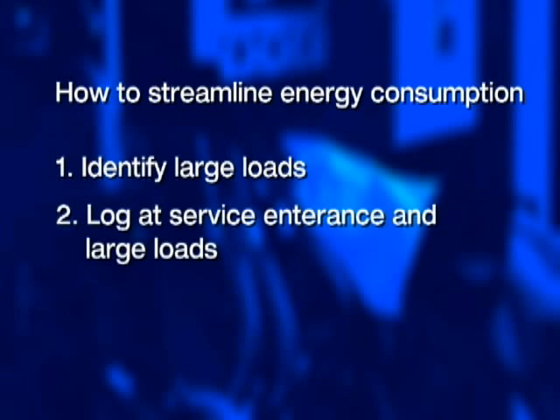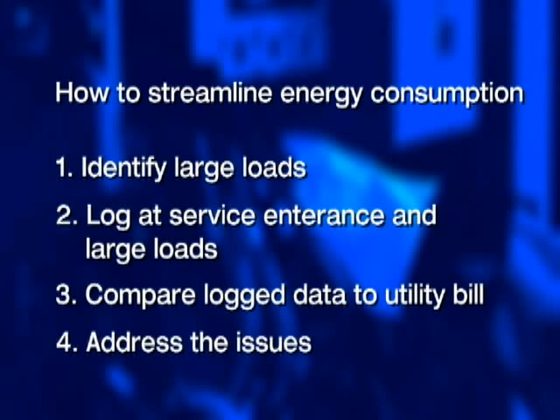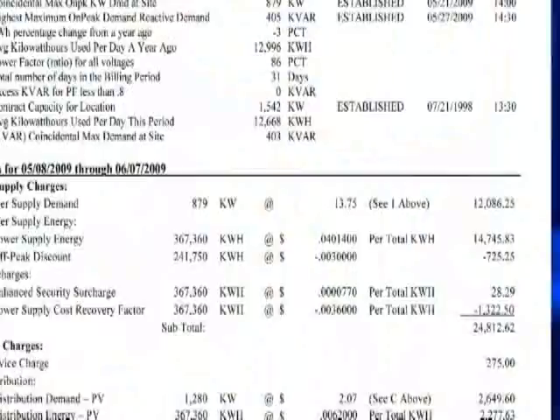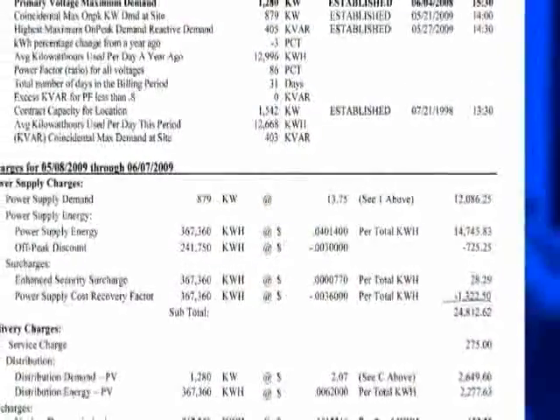Some of the energy logging steps we will take today to help you streamline your energy consumption are: identify large loads, log at service entrance, log each large load, compare log data to the utility bill, and address the issues that are revealed. Review your kilowatt hours, peak demand, and power factor charges.